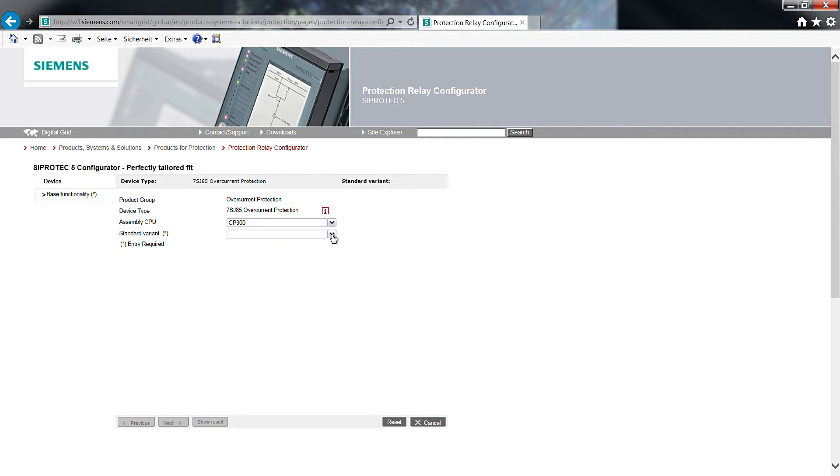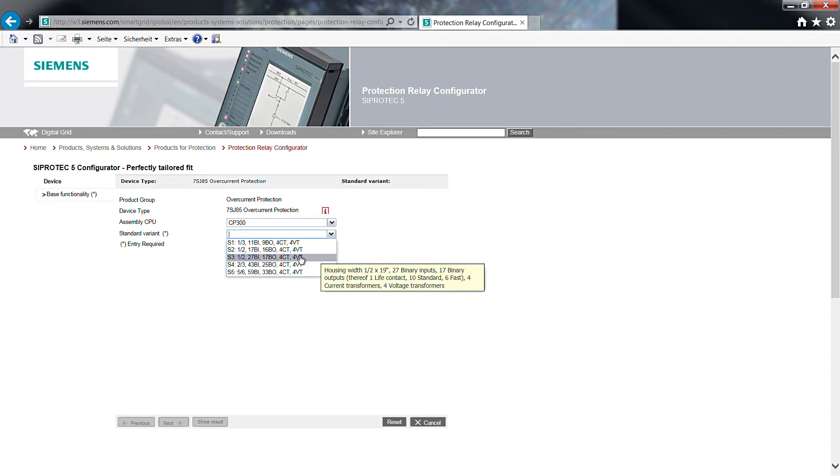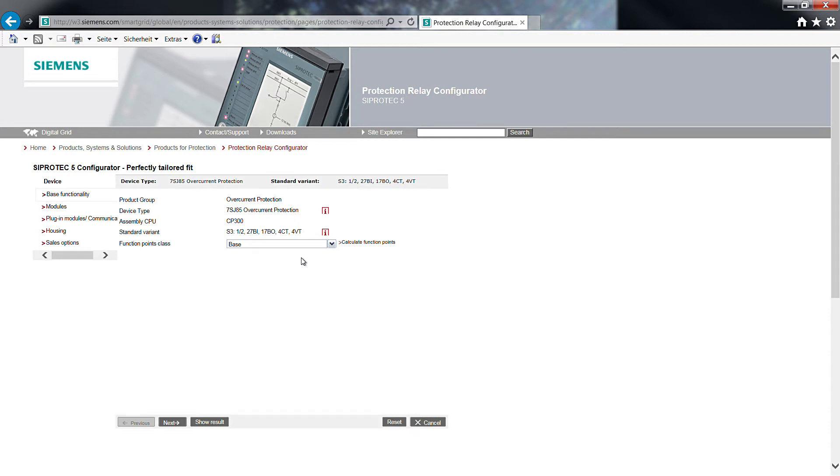According to the required number of binary inputs and outputs, you select the standard variant S3 with 27 binary inputs, 17 binary outputs, 4 current transformer and 4 voltage transformer measuring inputs in a half-size 19-inch rack case. You can adjust the selected standard variant to your requirements as you go along.